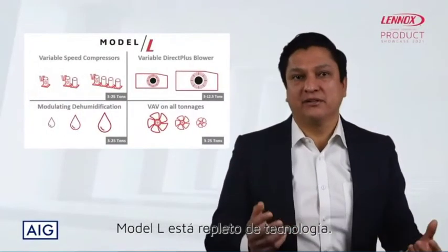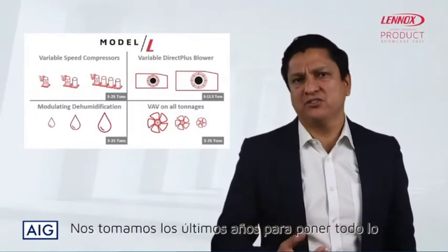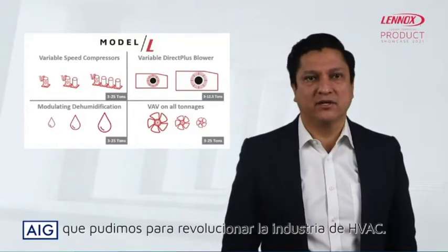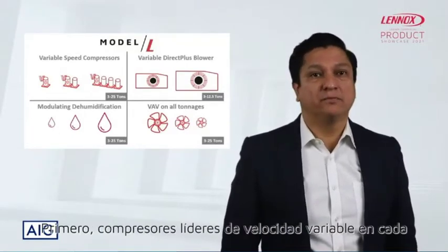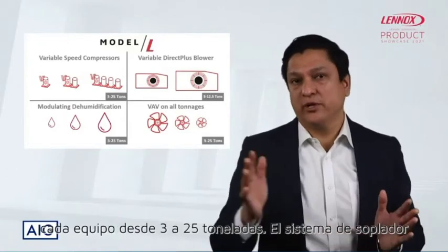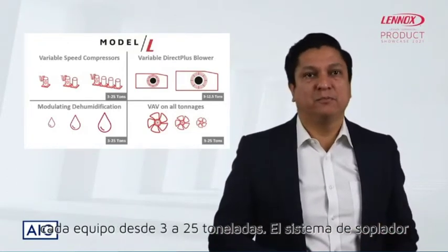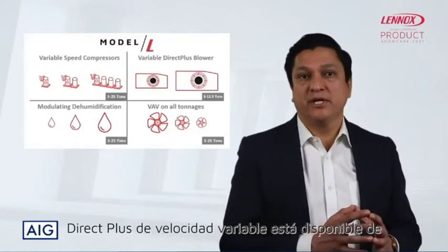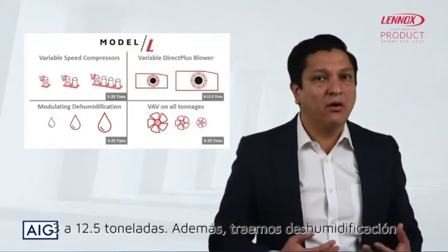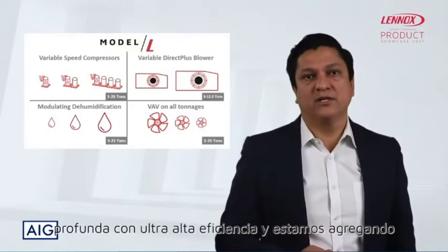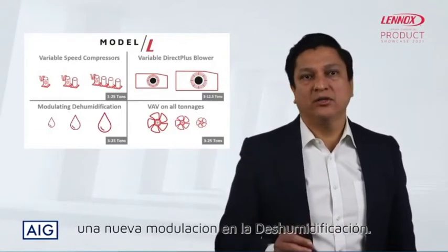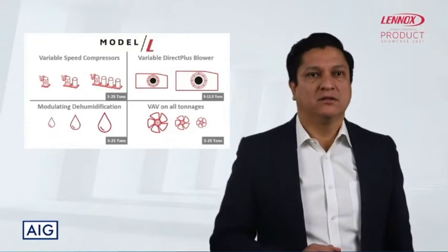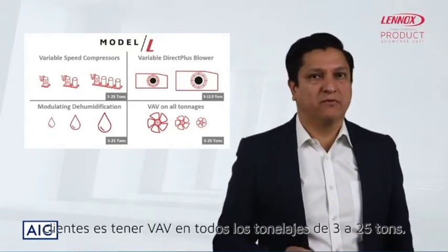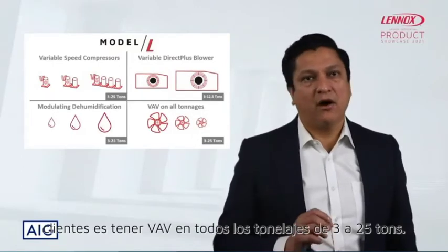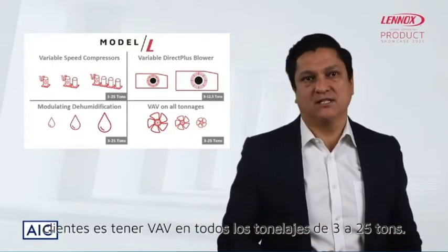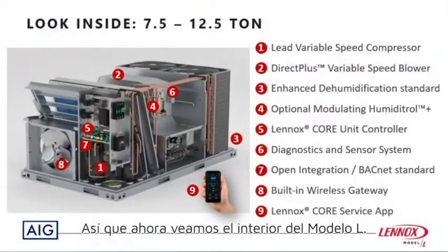Model L is packed with technology. We took the last few years to put as much as we can to revolutionize the HVAC industry. First, lead variable speed compressors in every box from 3 to 25 tons. Next, the variable speed direct plus blower system is available from 3 to 12 and a half tons. And we not only bring dehumidification in ultra high efficiency, we are introducing an all new modulating dehumidification. And one of the features that we've heard from you through those focus groups is VAV on all tonnages from 3 to 25 tons. So let's take a look inside the Model L.